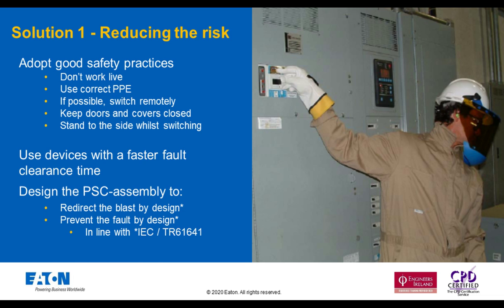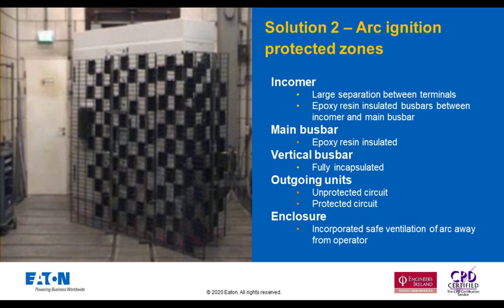So let's talk more about the IEC standard 61641, which covers arc verified assemblies and protection classifications. Plus, we'll talk about arc mitigation systems like arc quenching technologies in a little more detail in the following slides. So, as you can see, in solution 2 the switchboard is designed with arc ignition protected zones, what we commonly know as arc-free zones, and this is by application of design.